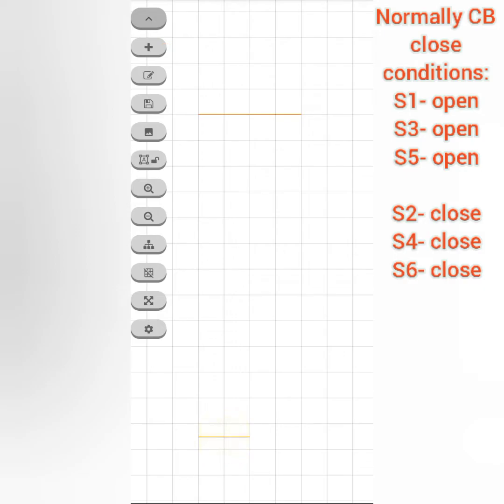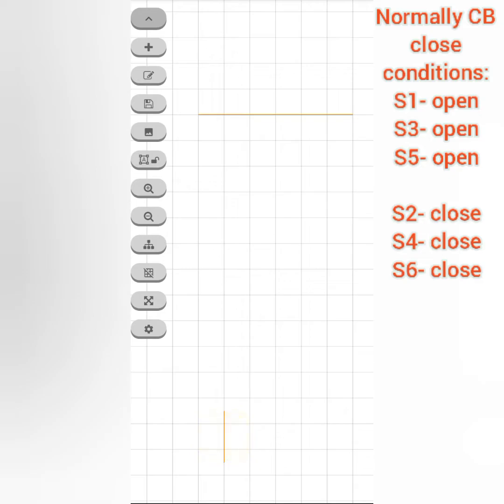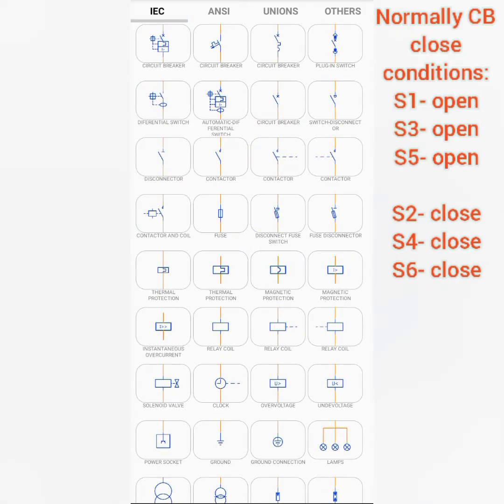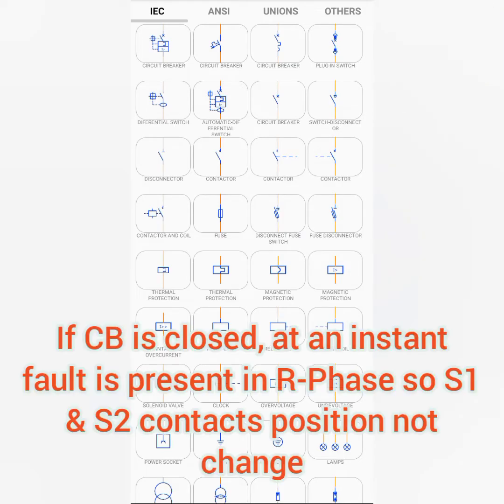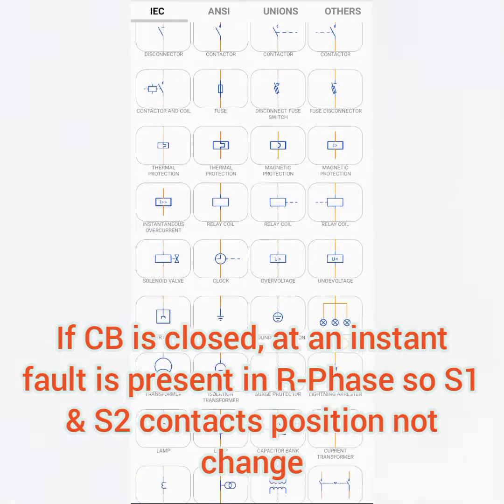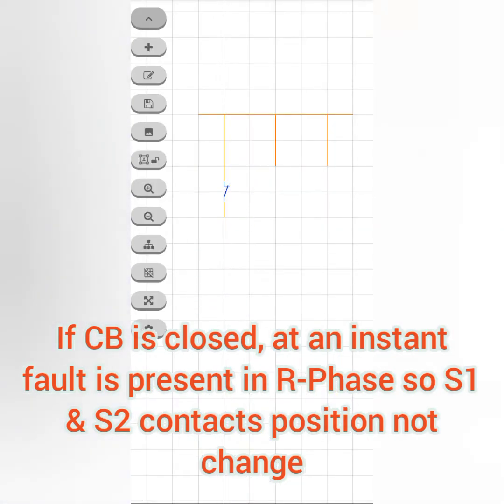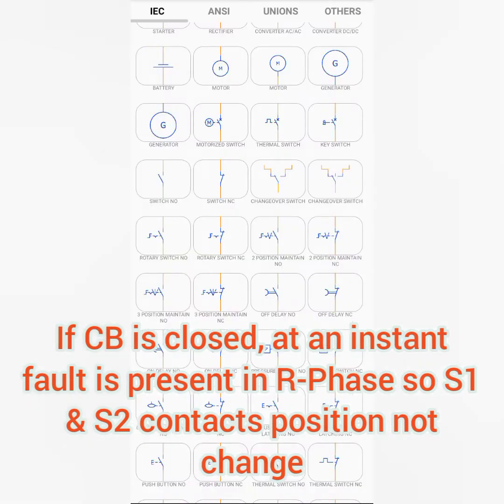Now we are seeing the diagrammatic representation of the PD timer. When the breaker is closed, the auxiliary contact positions automatically change — S1, S3, and S5 should move to open position and S2, S4, S6 should move to closed position. But due to a fault in the R phase, the S1 and S2 positions will not change. So the fault is present in the R phase and the PD timer will initiate after a specific time, automatically sending the trip command to all three phases.